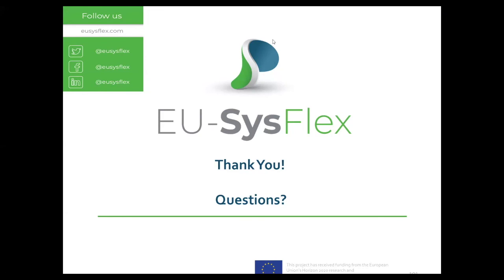For the inertia scarcity in the current all-island system, we have a synchronous inertial response product. That product essentially incentivizes conventional generators to reduce their minimum generation. So if a conventional generator reduces its minimum generation level, it can still run at that point, and that frees up space for renewable generation to be integrated into the system. So there could be a myriad of solutions, but the approach EU-SysFlex has taken is that any solutions are wrapped under a system service framework, as long as that's been well considered and thought out - you could have a number of solutions.